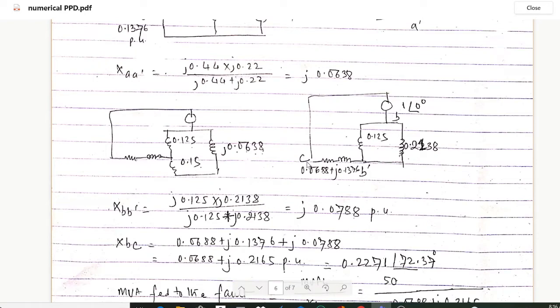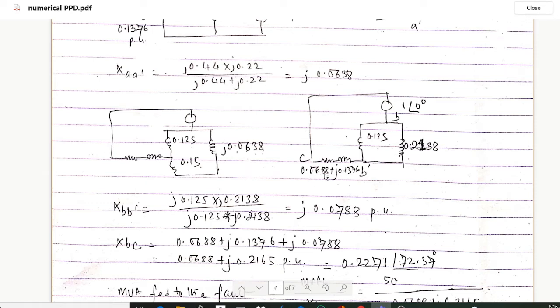Defining point B and B', X_BB' is found by placing the appropriate branches in parallel, giving j0.0788 per unit. Then X_BC from point B to C is obtained by adding the feeder impedance 0.0688 + j0.1376 to the parallel combination j0.0788, giving X_BC = 0.2271 at an angle of 72.37 degrees.